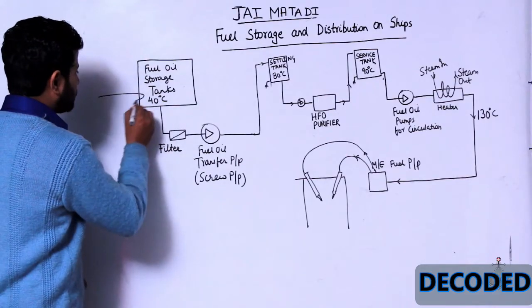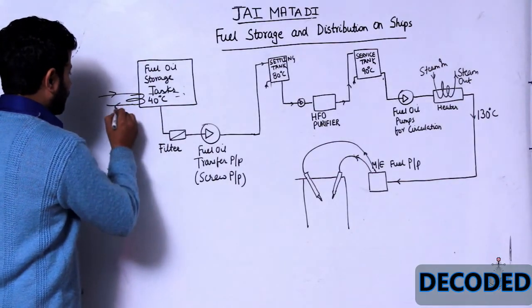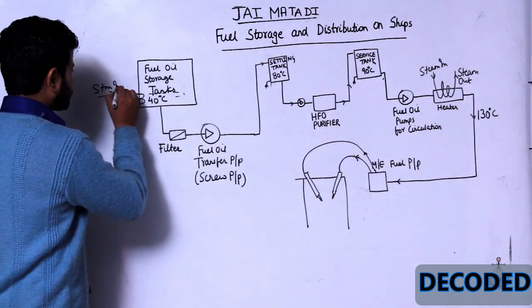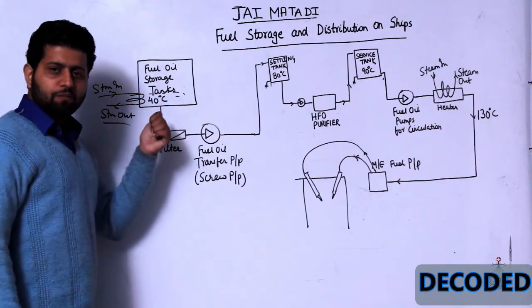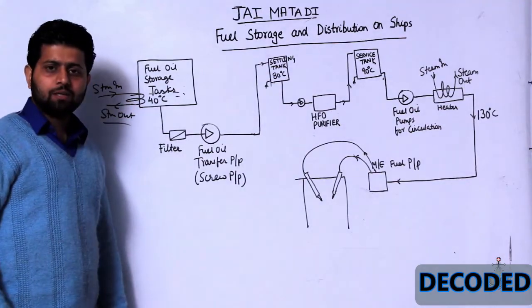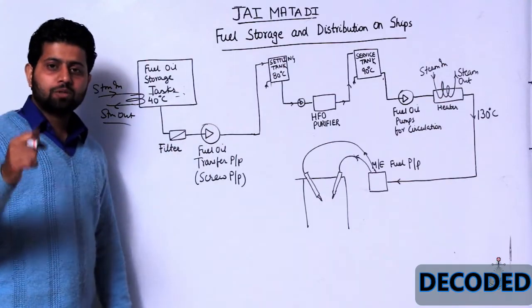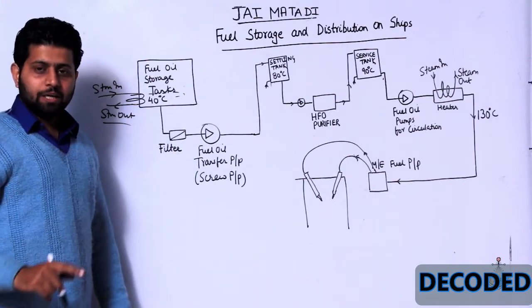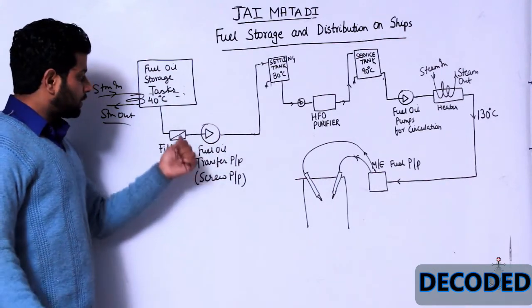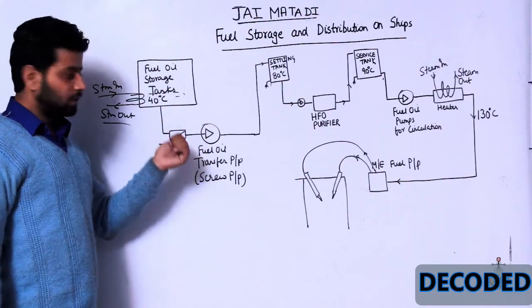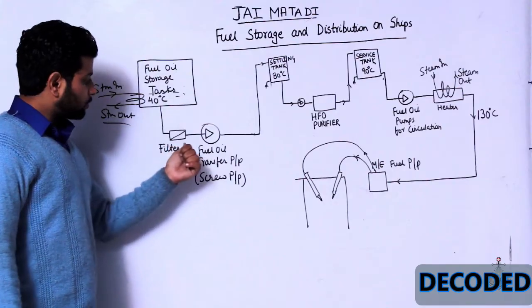In the storage tanks I have steam coils which go throughout the tank — steam in and steam out — and we maintain a temperature of around 40 degrees centigrade. We must ensure the temperature is always above the cloud point and pour point. If it is less than the pour point, the oil will not flow, and if it is less than the cloud point, the filter will get choked.